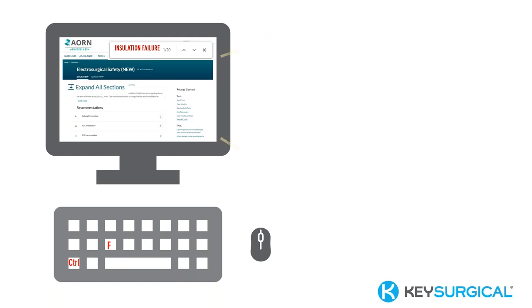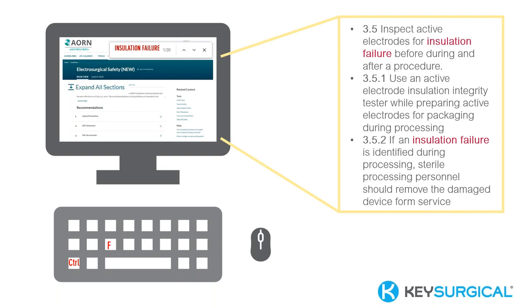And finally, here was the example I was looking for, the 2021 updated electrosurgery guideline. It was 3.5 that says inspect active electrodes for insulation failure before, during, and after a procedure. 3.5.1 says use an active electrode insulation integrity tester, say that 5 times fast, right? While preparing active electrodes for packaging during processing. And 3.5.2 says if an insulation failure is identified during processing, sterile processing personnel should remove the damaged device from service. So it made it a lot more efficient use of my time to get to exactly what I needed by a few tools.